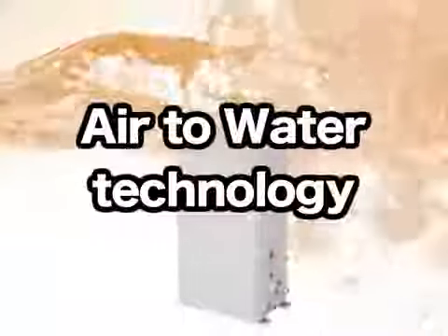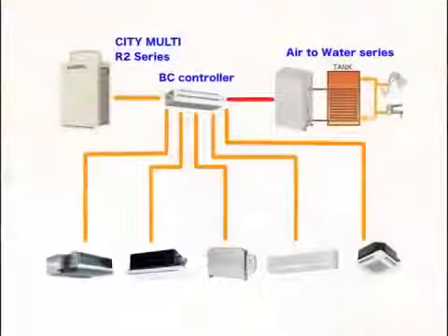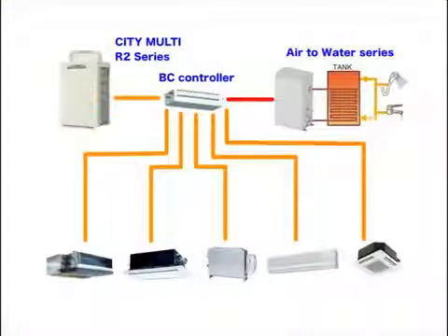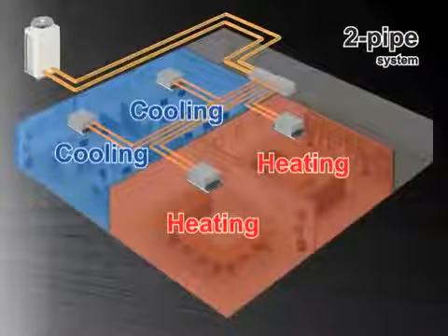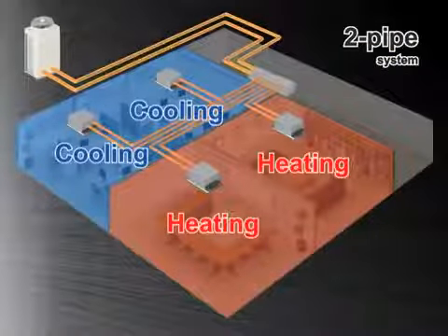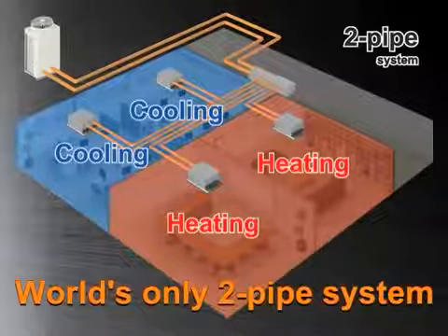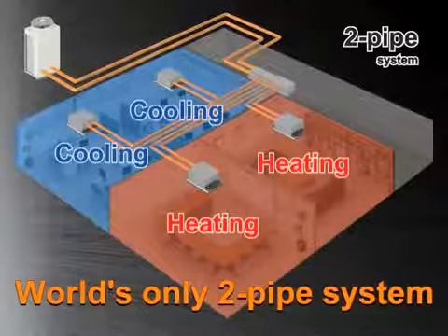Now, let's take a closer look at the brilliance in our air-to-water system. The air-to-water technology lies within our R2 system. Our R2 system is designed for simultaneous heating and cooling with 2 refrigerant pipes, as opposed to the market conventional 3.